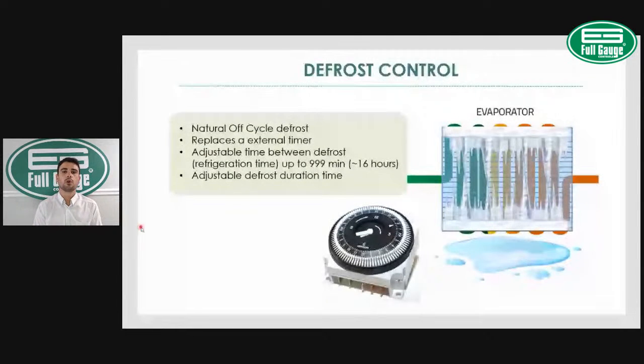Once you're working in cooling mode, the MT512 provides an off-cycle defrost capability. What does off-cycle defrost mean? It means the system will work under refrigeration for a configurable time, which can be an interval of 4, 6, 8, or 12 hours, depending on the application. Then the system will stop for 20, 30, or 40 minutes, at a user-definable interval, to perform that defrost cycle.